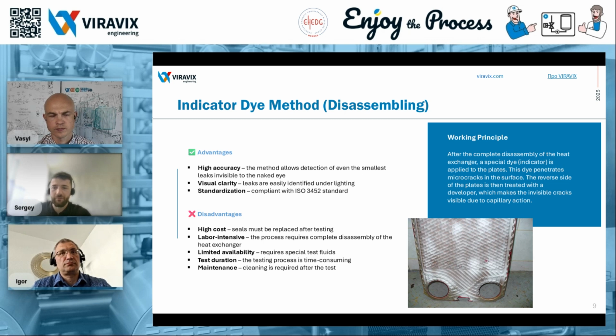The test requires full disassembly of the heat exchanger, and afterward, it must be completely reassembled. Limited accessibility. The method requires special testing fluids. Long testing time. The process can take a very long time. At some facilities, it may even stretch over several days due to the large amount of work involved. And finally, maintenance, flushing is required after this test.